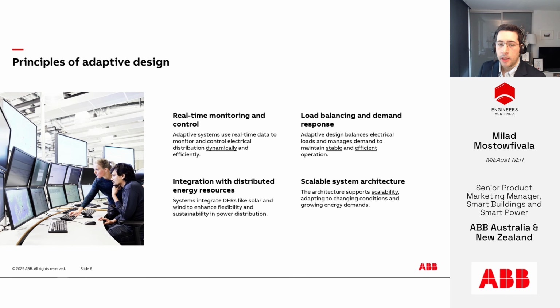So what are the principles for creating an adaptive design to mitigate these challenges? In my opinion, I've grouped these into four. Real-time monitoring and control is the first one, because our electrical distribution system requires a dynamic response in operation rather than a fixed operation compared to the past. Creating an adaptive system that can be dynamically controlled and monitored is very important, which requires implementing real-time monitoring.